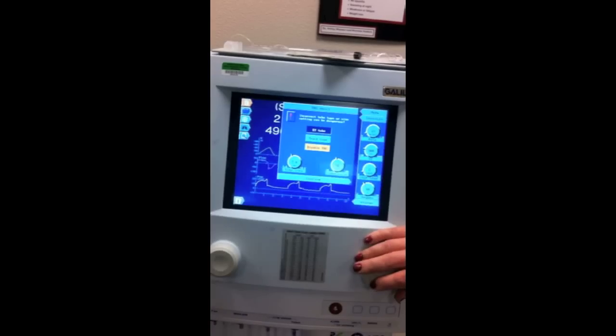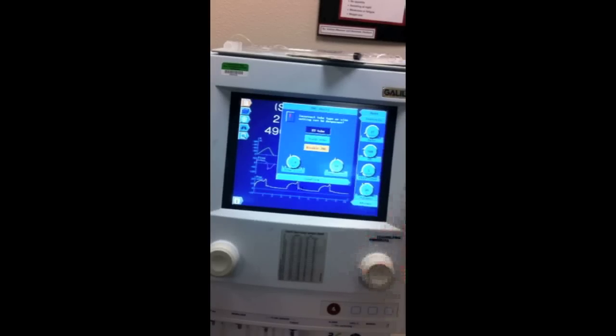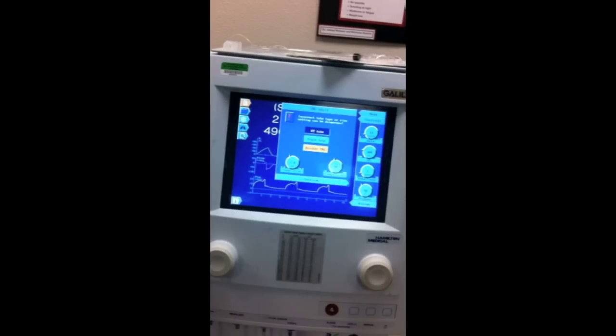The tubing compliance thing that's talking on the book, that's volume, right? Tubing compliance? Yes, you know how it calculates how much is lost on the circuit? That's something different. This has to do with the ET tube specifically and how much extra support we need to give our patient to compensate for the resistance from trying to breathe through a straw instead of not a straw. The compressible volume, or tubing compliance, has to do with the circuit. So don't confuse the two, they're different.